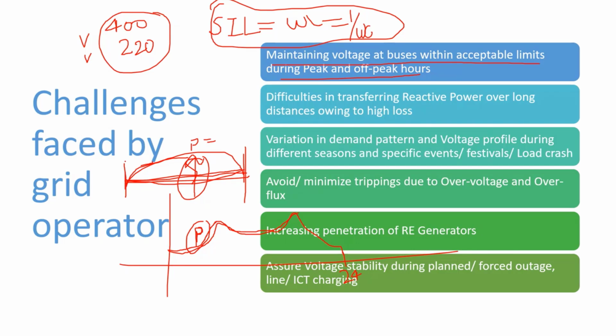And if these vary, this will also directly impact the voltages of the individual nodes or substations through which these lines are connected, because there will be reactive power variation due to the change in loading of the transmission line. So during low loading, you will face high voltages, and during high loading, you will face low voltages. So here you may face low voltage in the system.